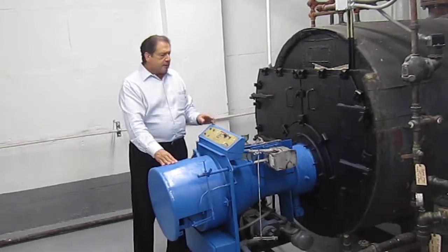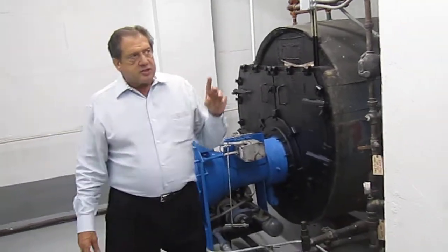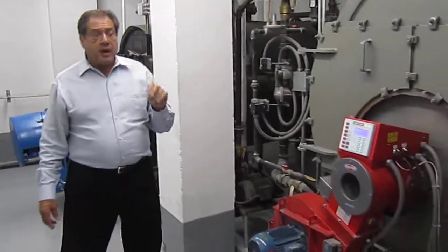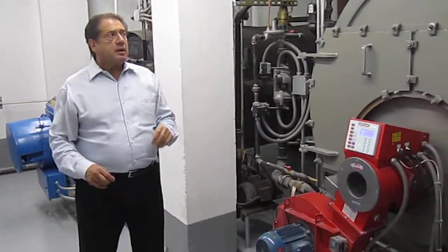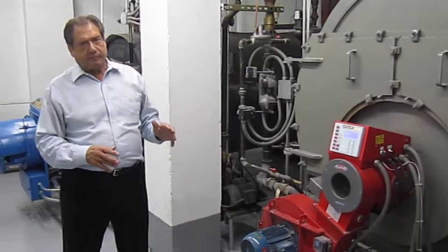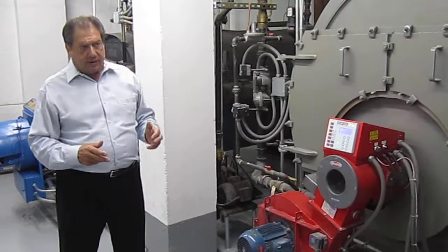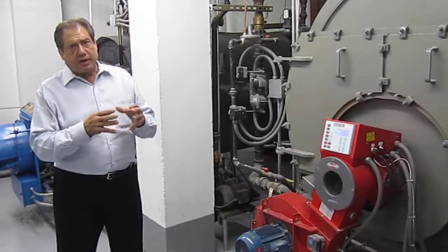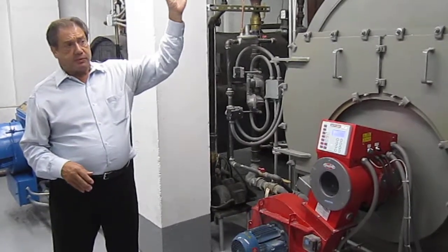The second question that was asked was steam traps. Steam traps on a steam system, it's very important to have them maintained on a regular basis. And a regular basis, in my opinion, is at least once a year. They need to be opened by a professional plumber or the building superintendent and make sure that they're clean. If those steam traps get clogged, then it will affect the heat distribution to the residents in the building.